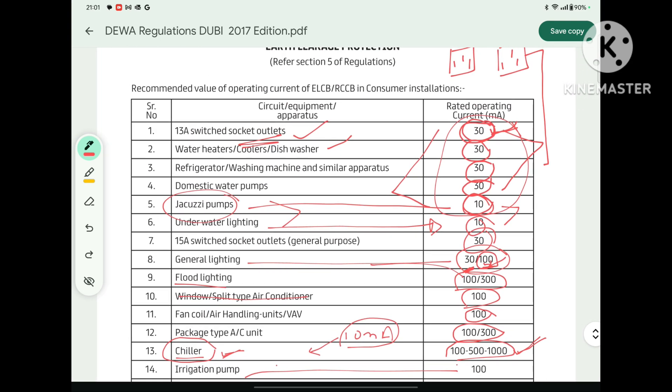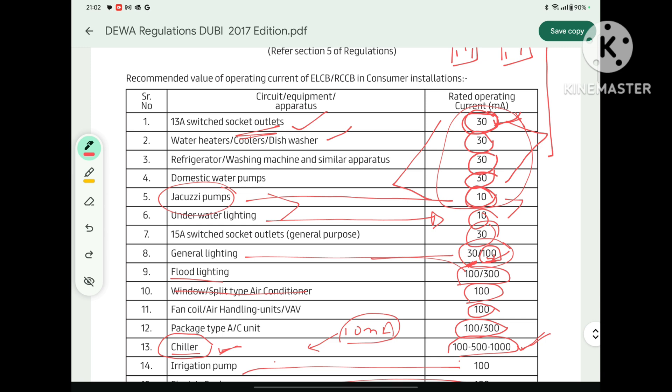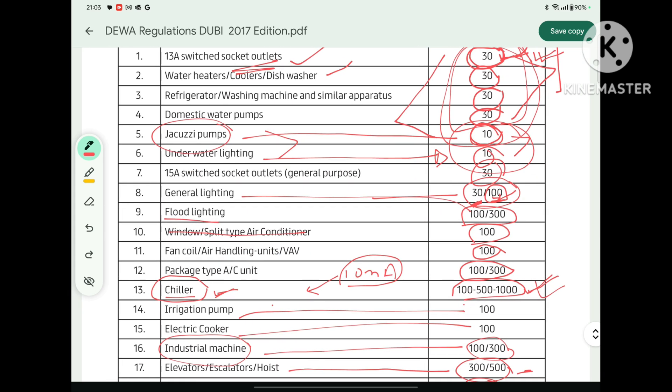DEWA has selected the ELCB rating for different types of loads very sensibly. Conceptually: loads which are in direct human contact should have a lower ELCB rating; loads in contact with the human body under wet conditions require an even lower ELCB rating. For larger equipment, the rating can go up to 1000 mA, because with a load of around 1000 kW, a 10–20 mA leakage is very obvious, and tripping the full system due to such leakage is not acceptable — it is called nuisance tripping. To avoid that, DEWA has selected a higher ELCB rating for larger loads.